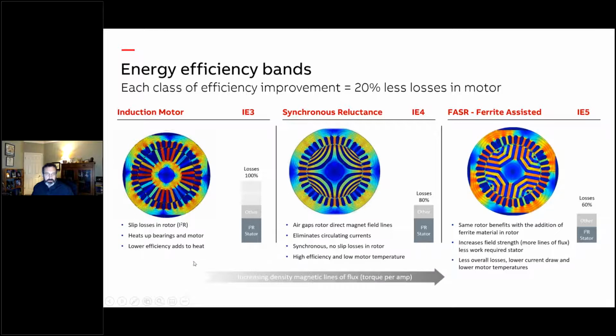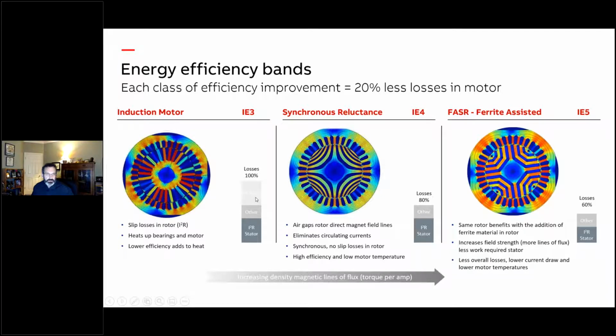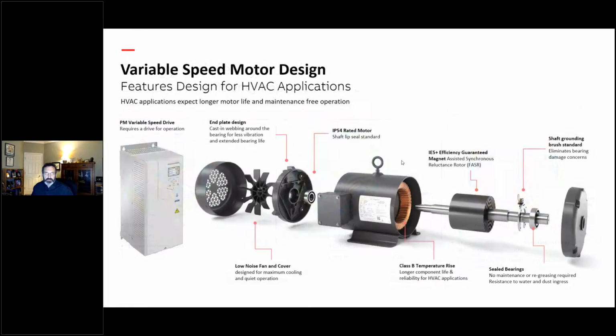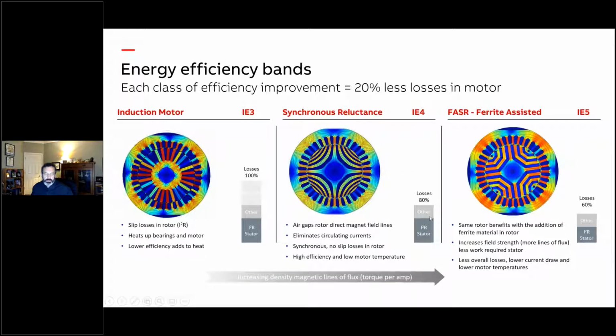All right. So again, here's what we already talked about. You've got increasing magnetic lines of flux, torque per amp as you go left to right here. You can see these nice, clean lines of magnetic flux through the air gaps versus the circulating currents over here. And graphically, this just shows you have your rotor losses in the standard induction motor. You eliminate those losses, which is about 20% of the motor. So again, each class of efficiency is 20% less losses in the motor. So if I eliminate 20% of the losses from the rotor, that's where I get to IE4. And if I eliminate 20% more of the losses with the stator, that's where I get to IE5 by adding the magnet material. All right.